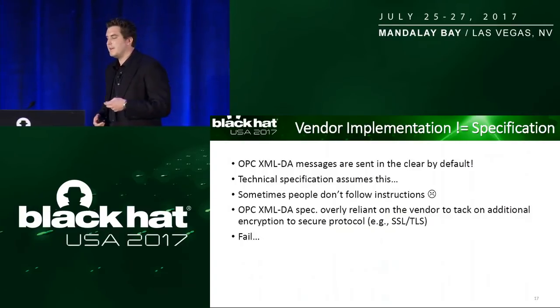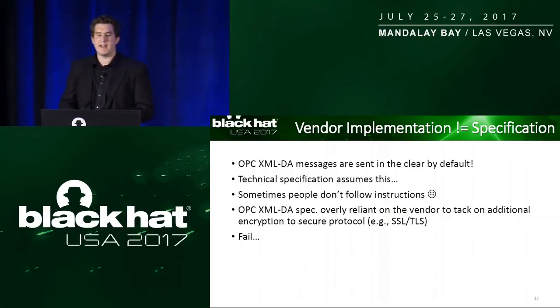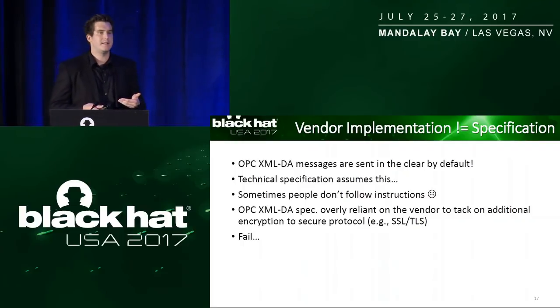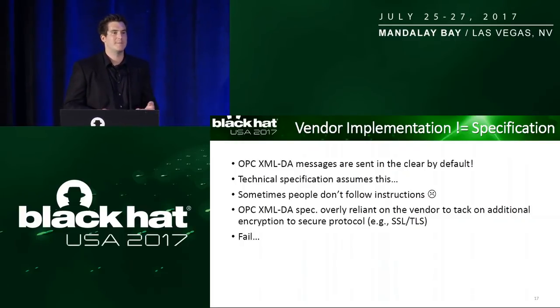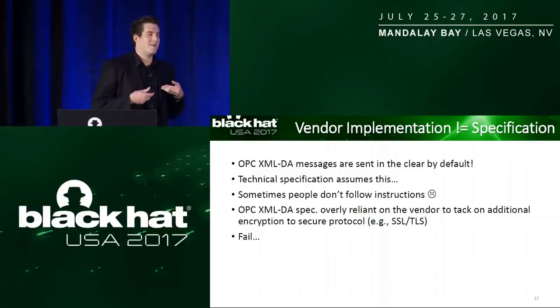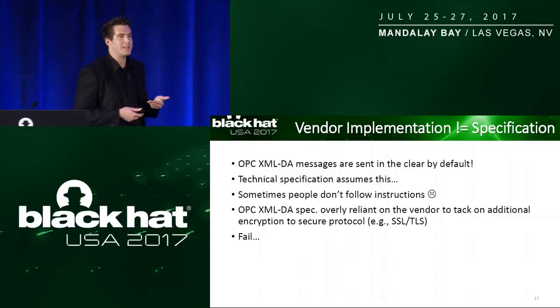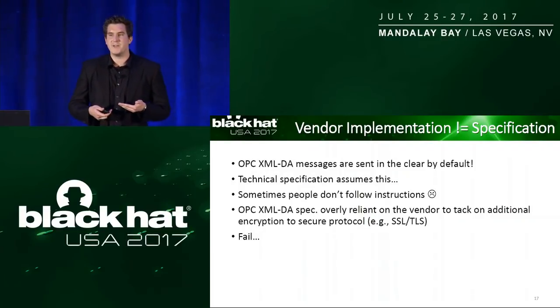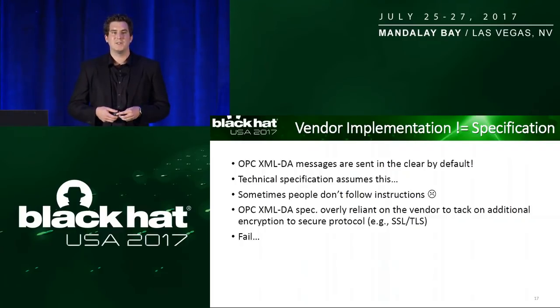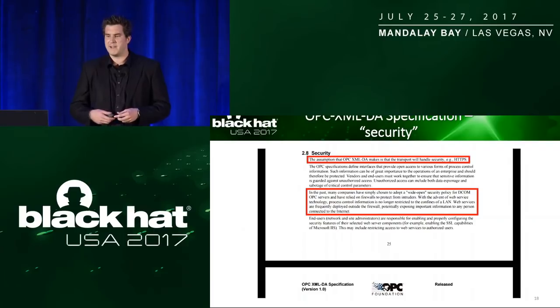If we take a deeper dive into the OPC XML-DA spec, it recognizes the fact that this is an insecure protocol, everything's transmitted in the clear. It says that if you're planning on using this in a production system, you're going to be using TLS or SSL to encrypt all of your communications, otherwise bad things could possibly happen. And here's exactly where it calls this out.